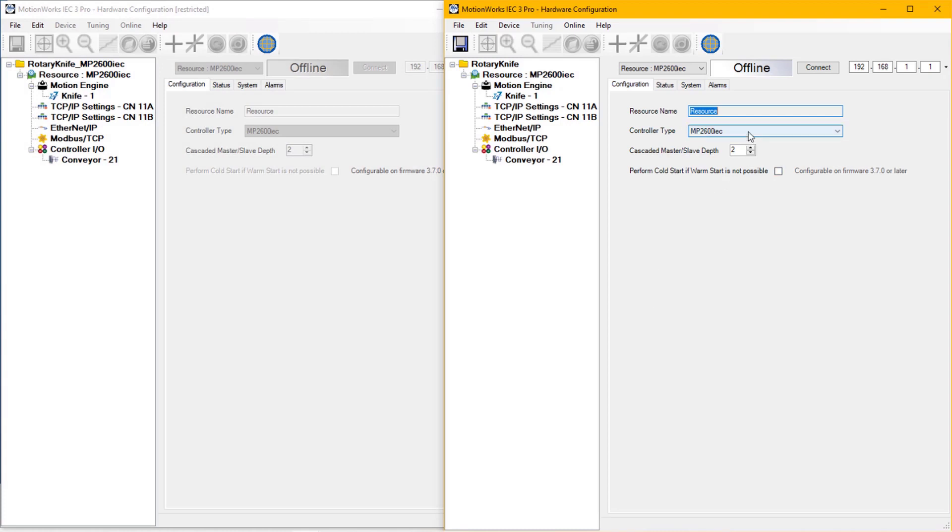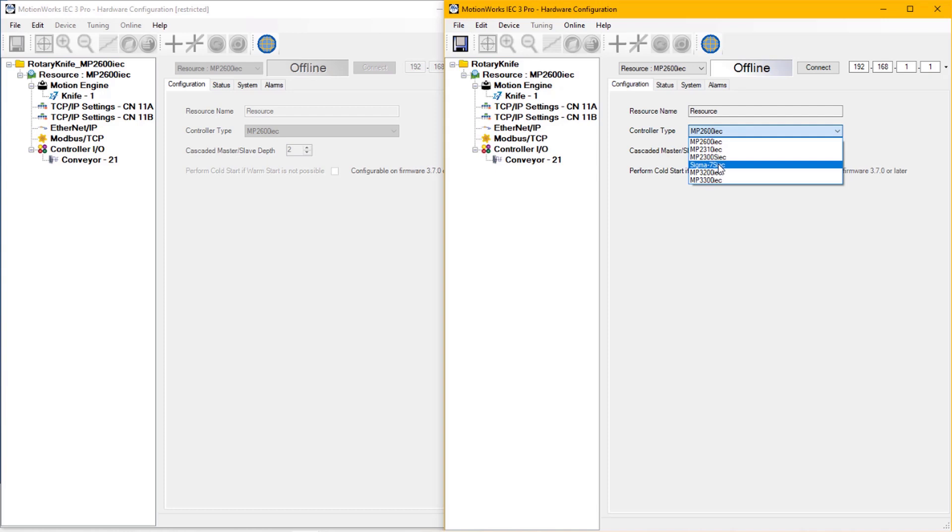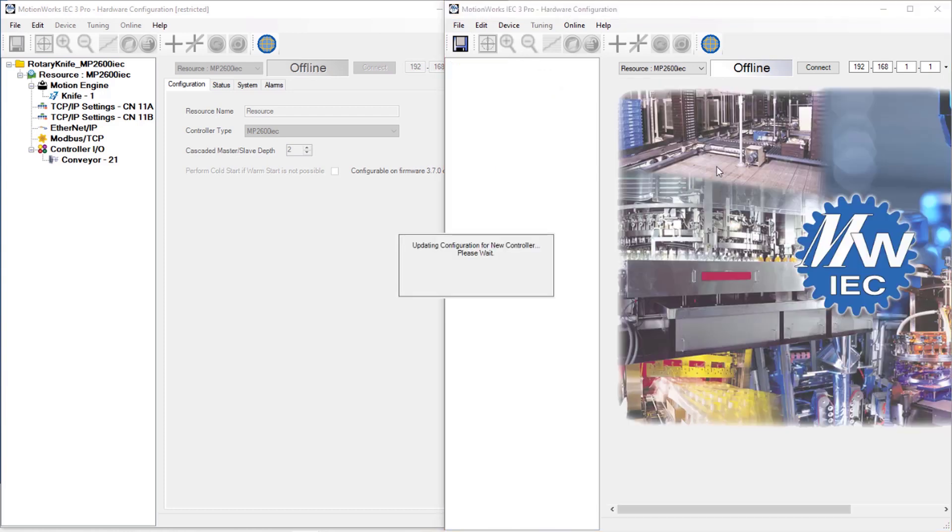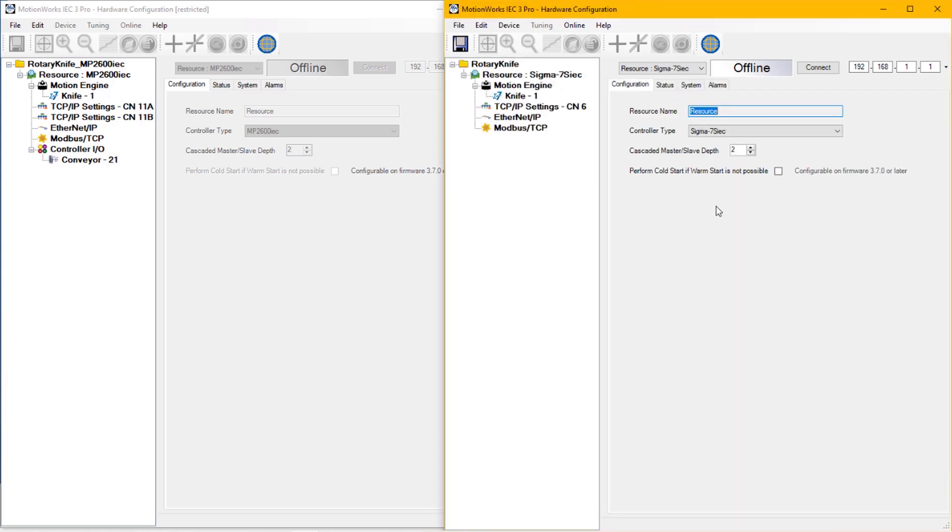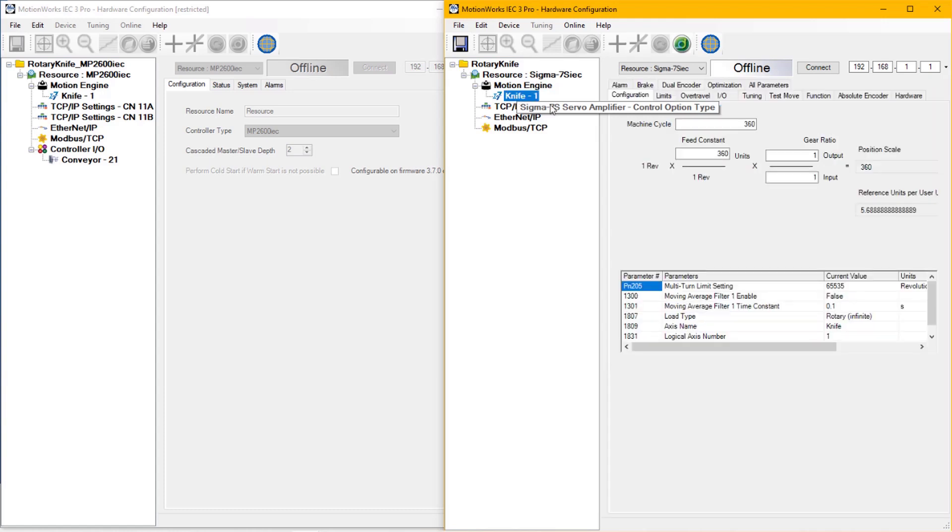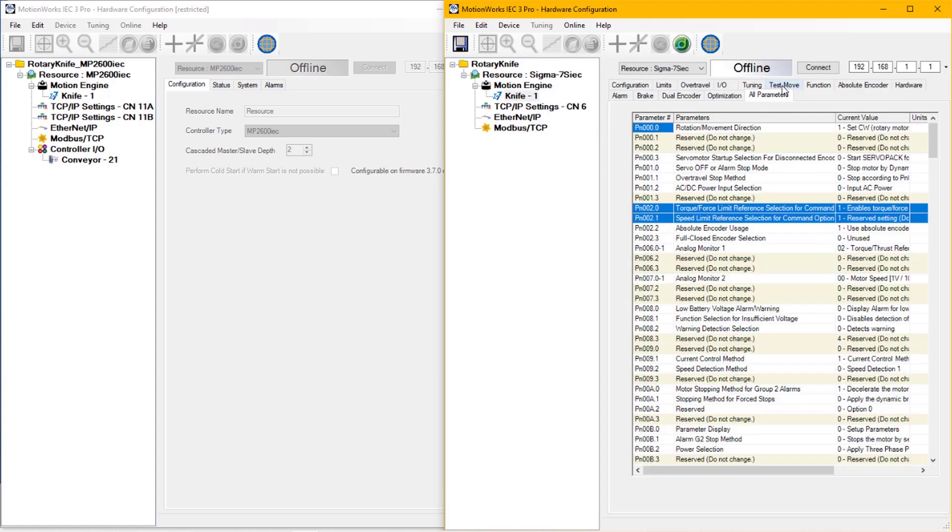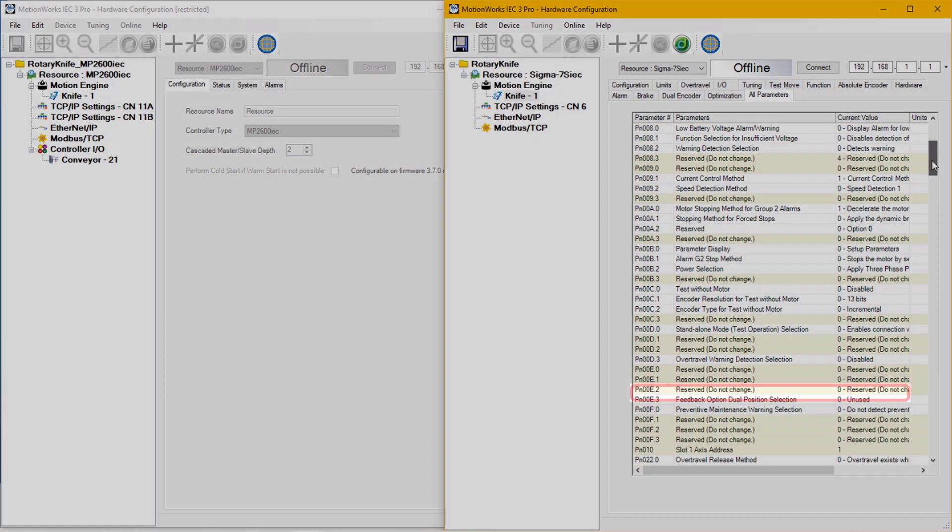I'm going to change the resource from MP2600 IEC to the Sigma-7S IEC. To enable the external encoder, I need to go into the knife axis and go to all parameters, and then find parameter PN00E.3.